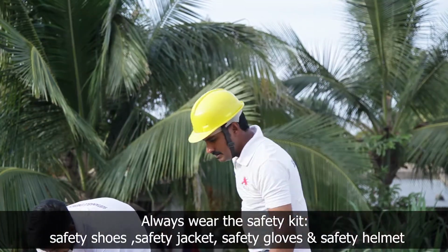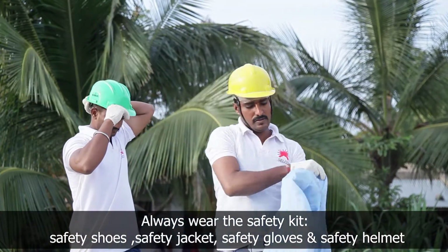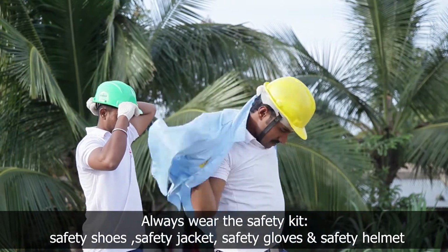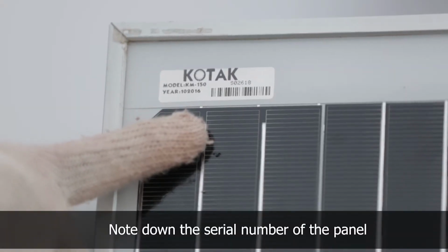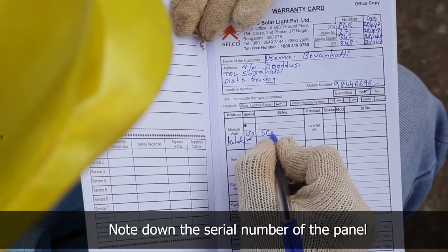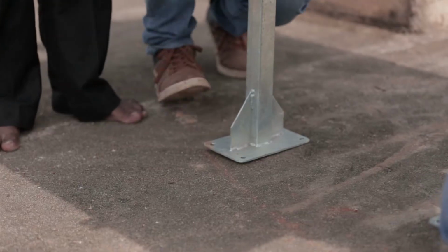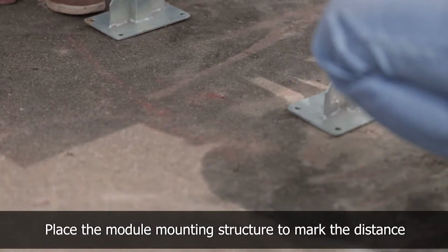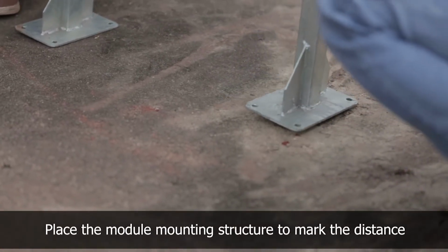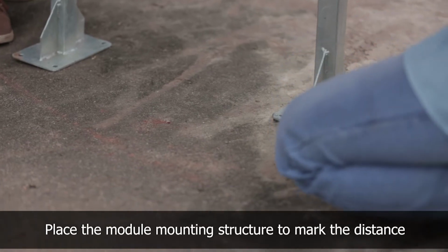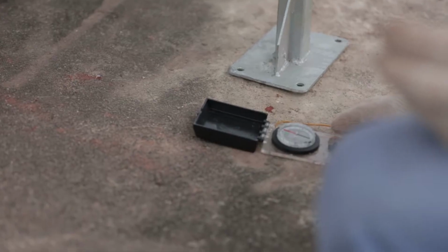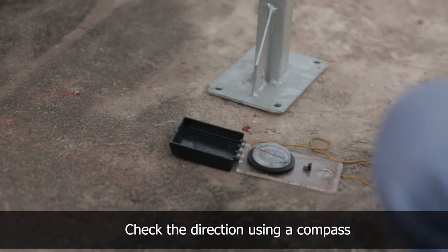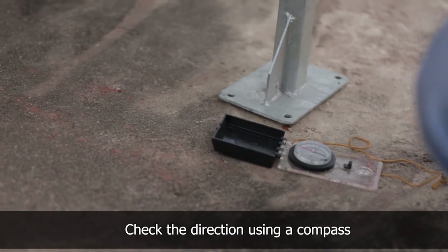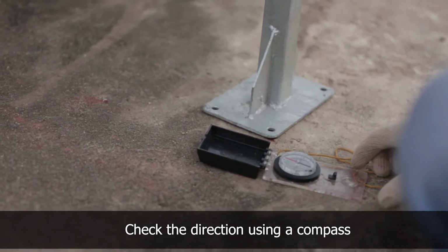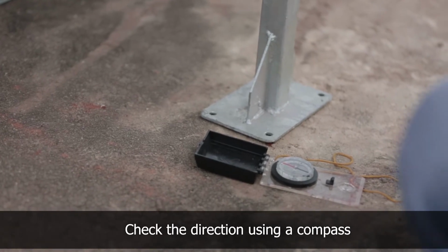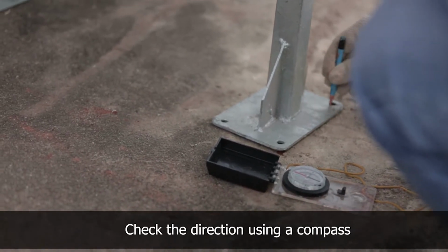Always wear a safety jacket, helmet and gloves before starting the installation. Enter the serial number of the panel and the battery for warranty. The panel and module mounting structure is temporarily attached for marking the distance between the stands on the roof. Check the direction using a compass and adjust the panel facing towards south direction with appropriate inclination as per the region for maximum radiation.